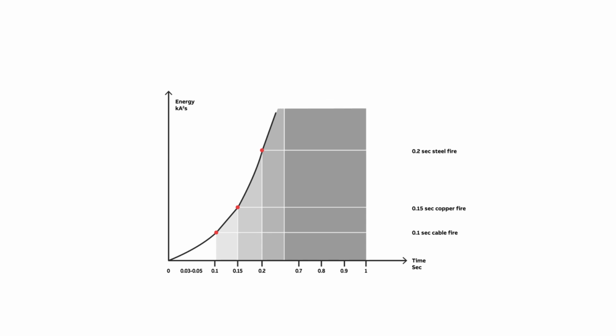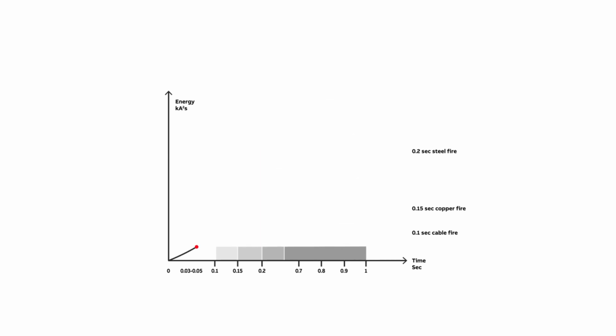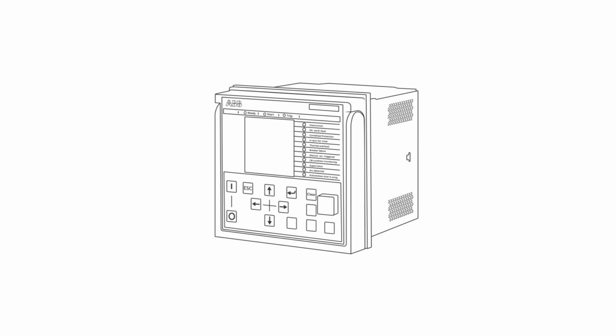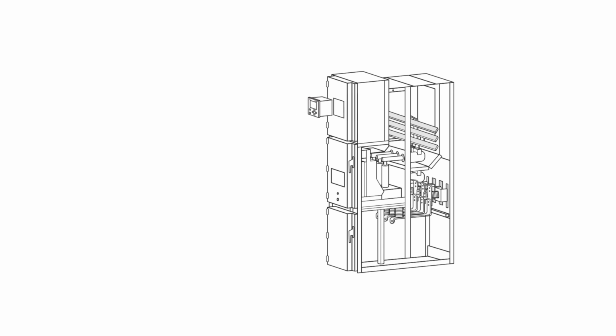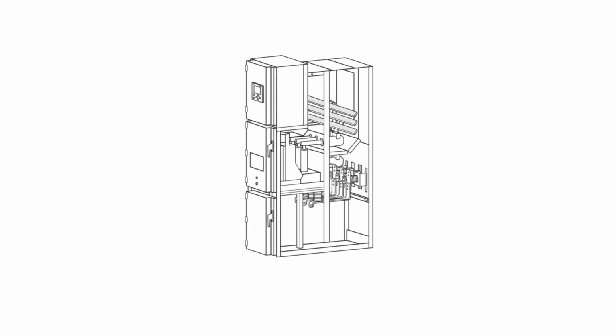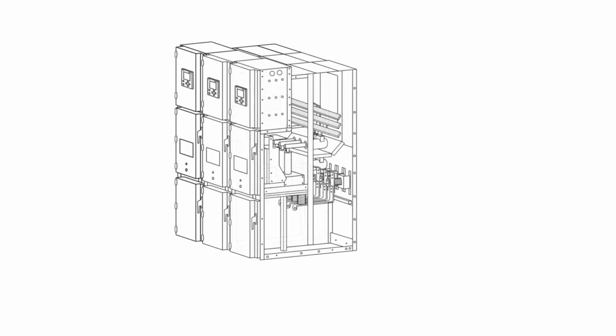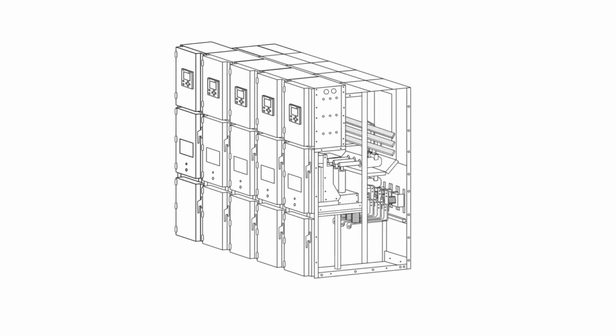Arc flash mitigation solutions can significantly reduce the impacts, improve safety for people, and drastically reduce the time required to repair switchgear. One example is a protection relay that detects the light and current of an arc flash. When an arc flash is detected, the relay sends a trip signal to the circuit breaker to ensure the power is interrupted within milliseconds. Let's look at an example where we have an arc flash protection scheme that covers a complete switchgear lineup.